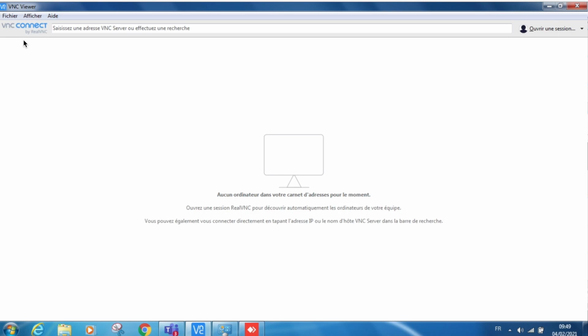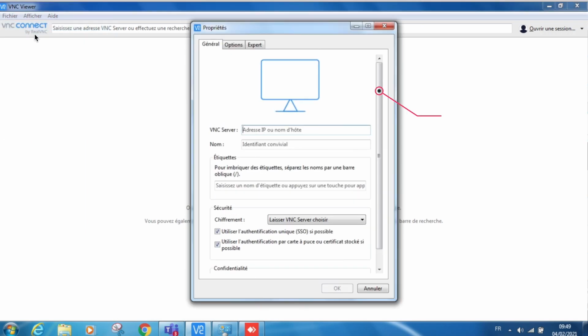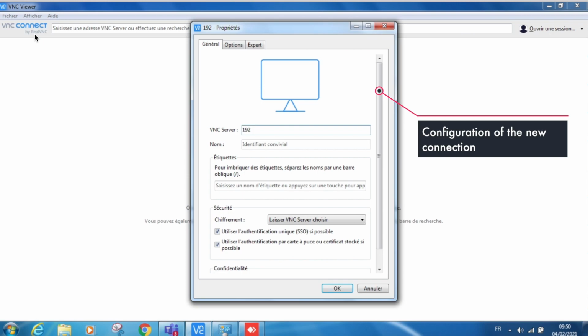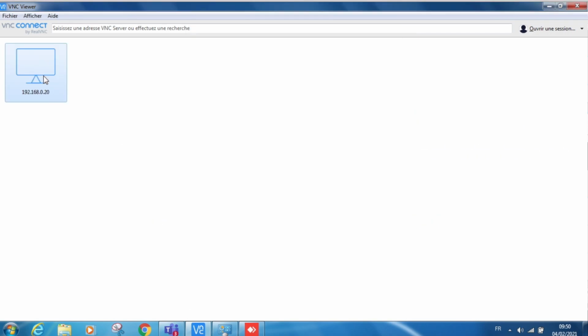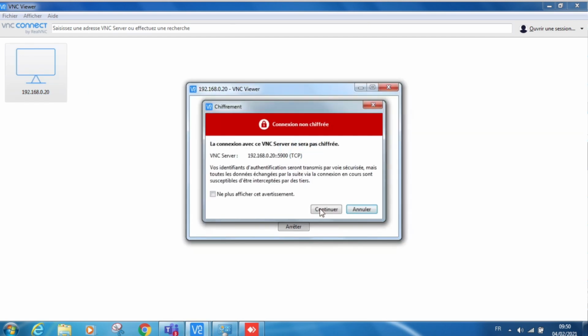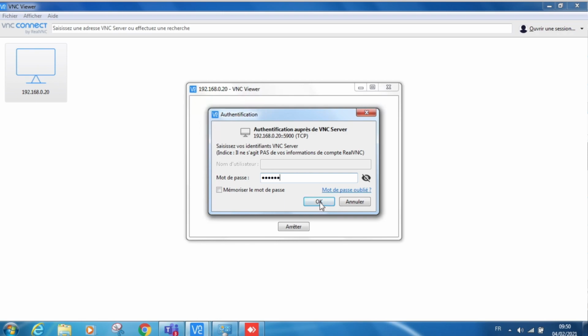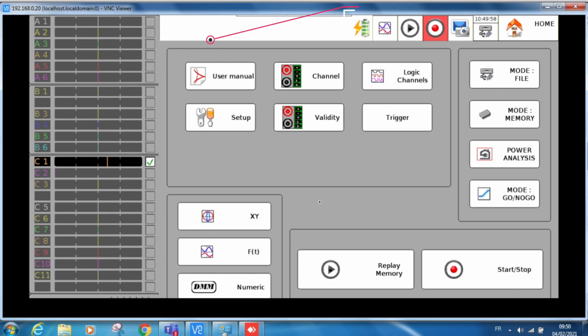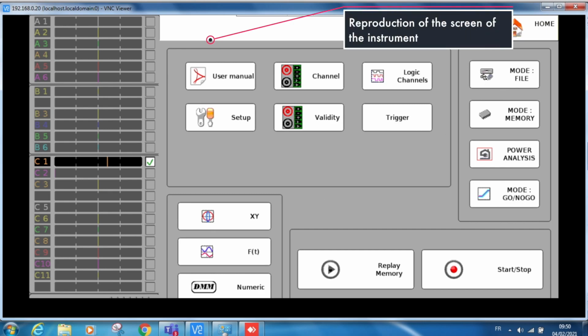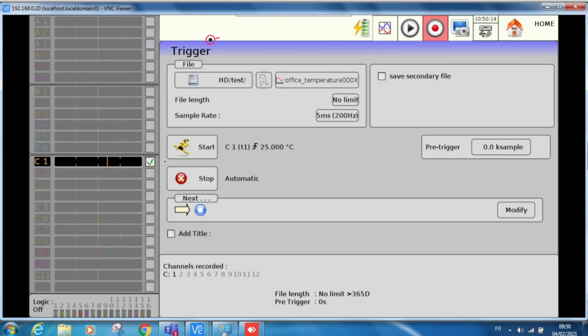The VNC Viewer software is free and can be downloaded from the internet. It allows you to have a reproduction of the screen of your instrument on your computer. The instrument has to be connected to your computer via an Ethernet or Wi-Fi connection. In the software, you first have to create a new connection. To do so, enter the IP address of the instrument. Access this connection and enter the password you previously entered in the DAS1700. The computer connects to the instrument and you get a copy of the instrument screen. You can now navigate through the menu and configure the instrument just as you would directly on the device.